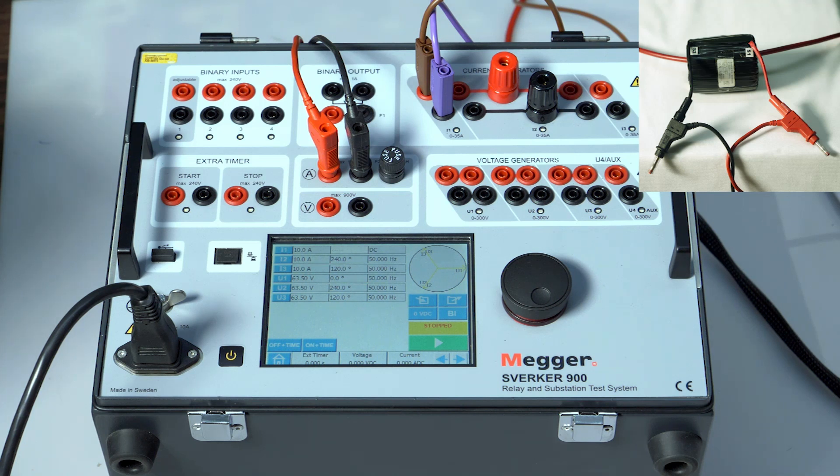CT testing polarity test. In this test the polarity marking on the CT should match with the drawing, as the indication of current flow plays an important role in protection.